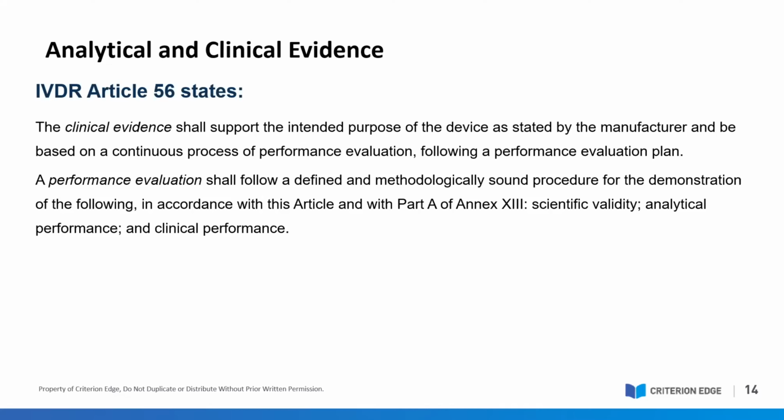Analytical performance, such as analytical sensitivity or analytical specificity, trueness, precision, which includes repeatability and reproducibility, accuracy, limits of detection and quantification, measurement ranges, linearity, cutoff values. All of those help you determine the appropriate criteria for specimen collection and handling and control. And it allows you to discuss things like interference or potential for cross reactions. Those are all comprised within your analytical performance data set.